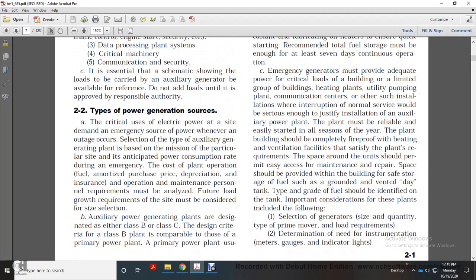Priority types of power generation for critical electrical power use require an emergency source of power whenever an outage occurs. Selection of the type of auxiliary generator power plant depends on the mission, anticipated power consumption rate during the emergency, cost of the plant, operation, fuel, type of drive, depreciation, maintenance personnel requirements, and future load growth requirements of the site.